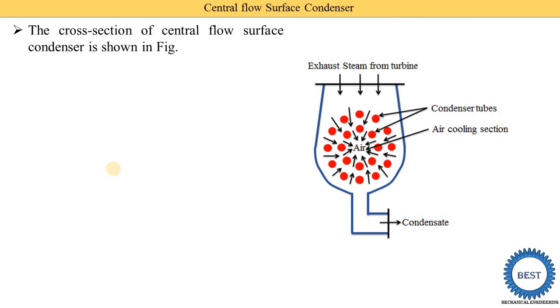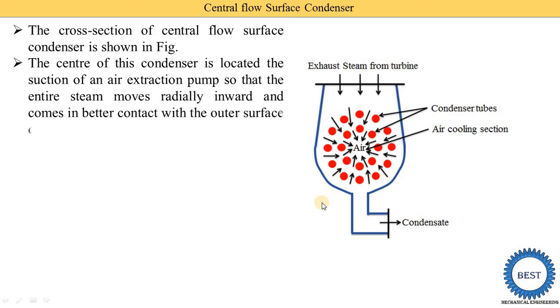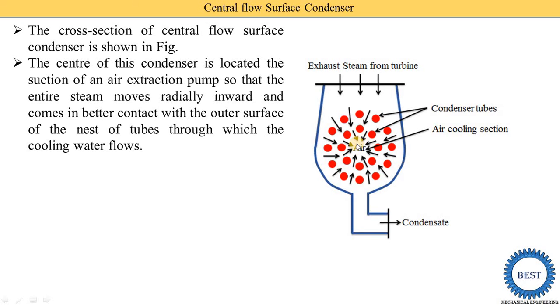The cross-section of the central flow surface condenser is shown in this figure. In this diagram, you can see that the center of this condenser is where the suction of the air extraction pump is provided. At the center, there is a suction pipe for the air extraction pump, so the entire steam moves radially inwards.